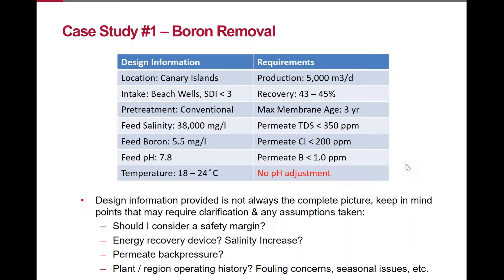One critical issue with this plant is that we're not allowed to use any pH adjustment to meet the permeate quality requirements — namely boron. As mentioned previously, boron rejection is heavily affected by feed pH. Typically, a way to boost boron rejection is to dose with NaOH to increase pH; however, in this case that's not allowed. The reasons can include avoiding operational issues with pH dosing and avoiding the cost of chemical dosing and installing a dosing system.